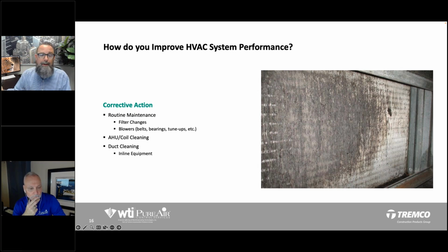So in this picture, you're seeing a pretty large chilled water evaporator coil. And you can see the kind of fouling that can get on this coil if you're not inspecting it routinely or cleaning it routinely. And so this kind of buildup on a coil not only, Steve, restricts airflow, as you know, but it's going to insulate that coil. And when that coil is insulated, it's like putting a wet blanket over it, right? So now this machine has to work harder.